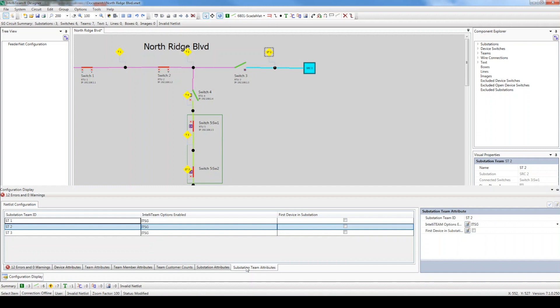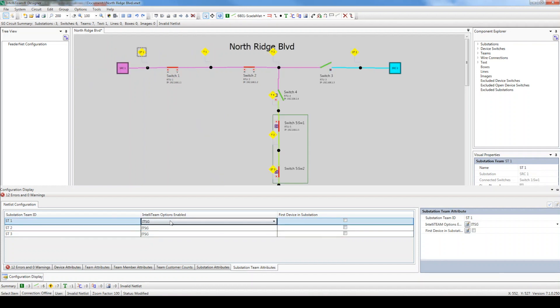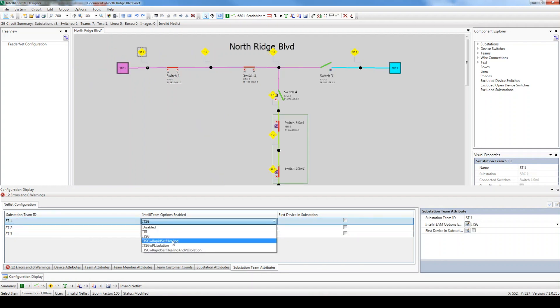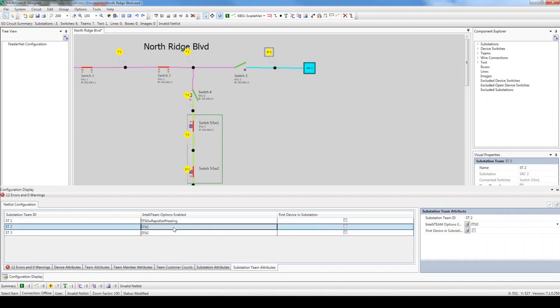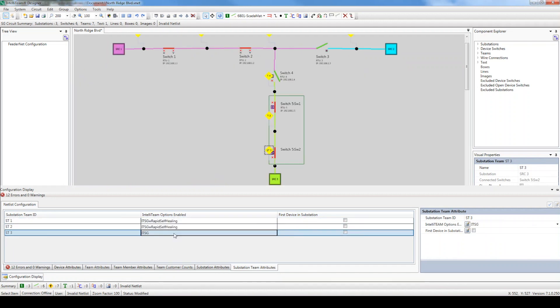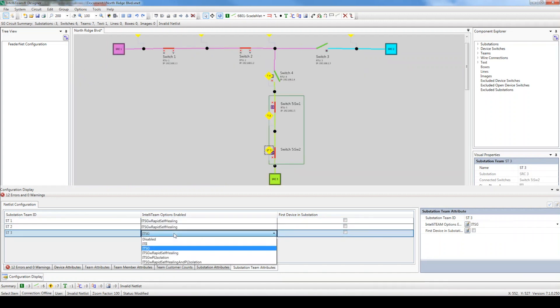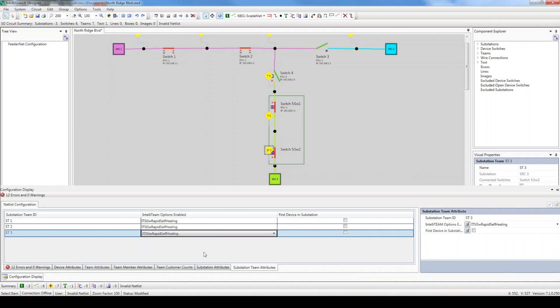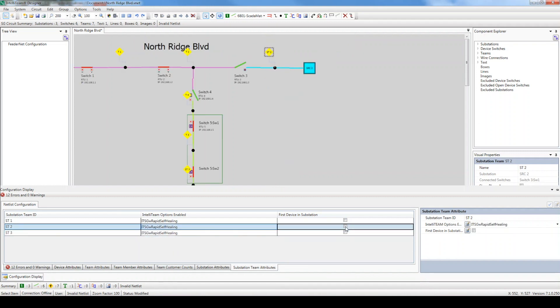Just like we did with the team members, set all the sub-teams to ITSG with Rapid Self-Healing. If the device nearest the source is installed in the substation, then select the First Device in Substation checkbox. In our case, the IntelliRupter and the Vista switch are both installed in the field, but the IntelliNode is installed on the substation breaker, so let's select the checkbox next to that source.